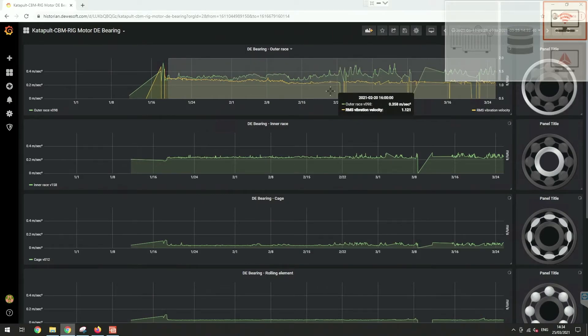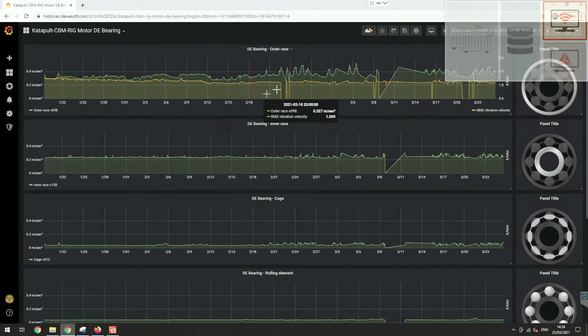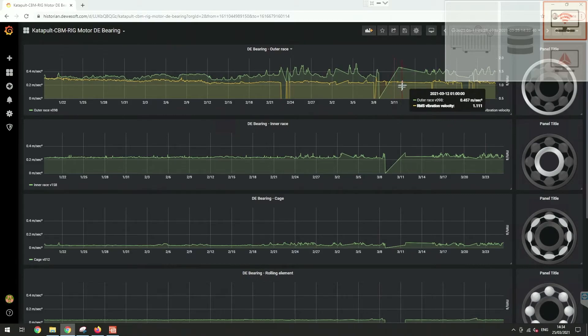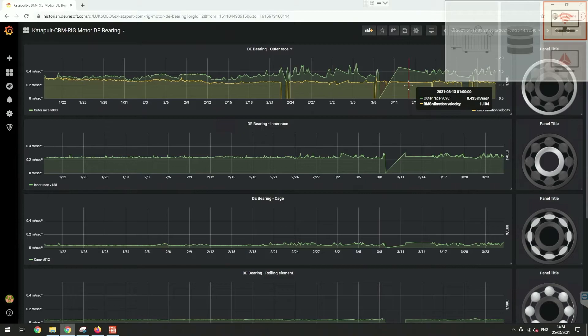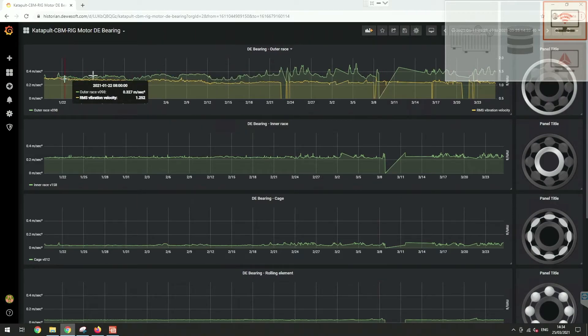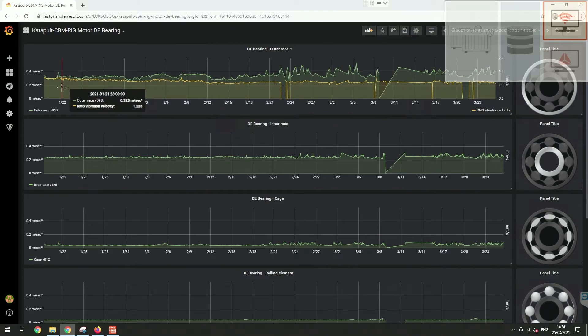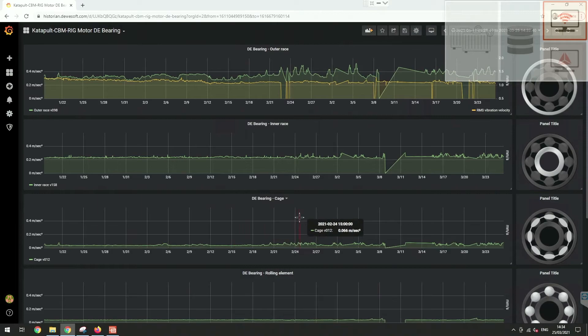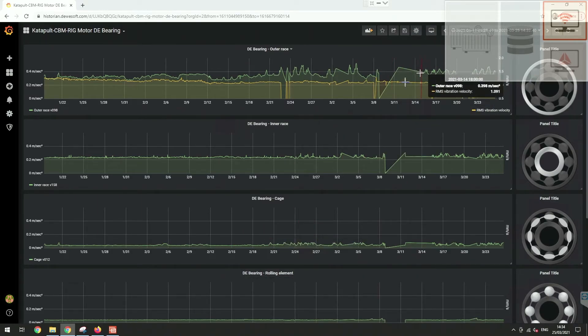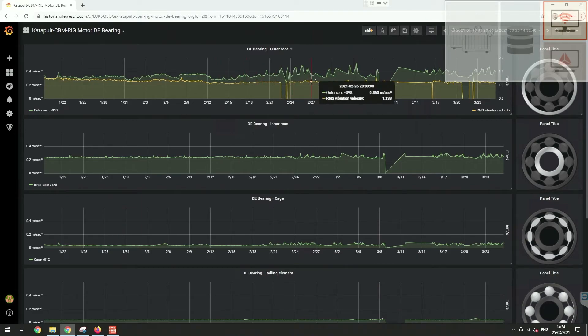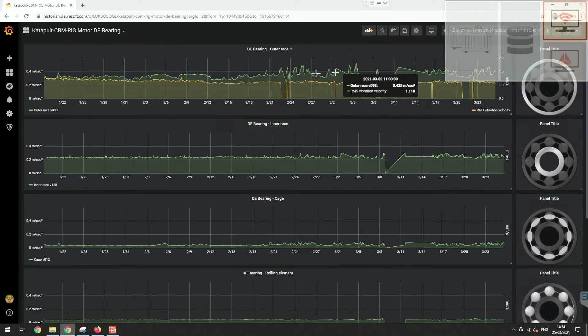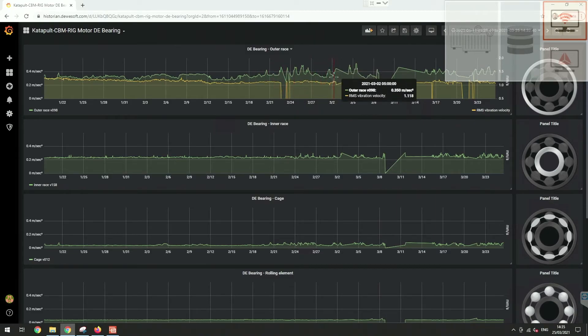Like this, you can see, let's zoom in into here. The orange line is just a reference. The orange line is the RMS vibration velocity, so this is what we get directly from the accelerometer almost without any fancy mathematics. You can see that it's just constant, more or less. But looking at this outer race amplitude, it's slowly growing. Over the last two months, this is from 22nd of January, as we are running this system, it's slowly increasing, and the other parameters are not really increasing. This gives us some indication that the outer race of the bearing might slowly get damaged. We will look through time to this trend, and if it happens to go up a lot, this can trigger some alarms. It will be interesting to see that in the future.